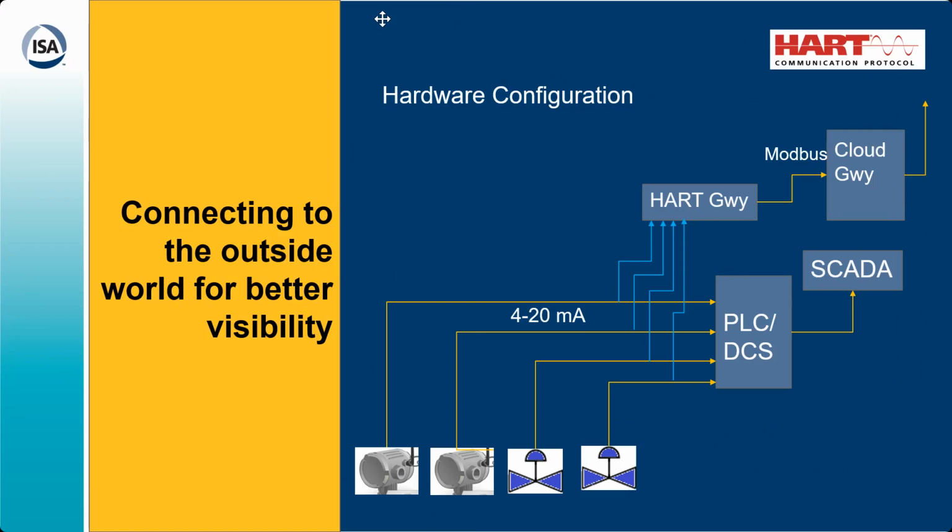See, the HART gateway has internal current sensing resistors. So you have to route the 4 to 20 milliamp line through these resistors, and it doesn't affect your 4 to 20 milliamp loop. The HART signal is available across that 250 ohm resistor, which is already there in the HART gateway.